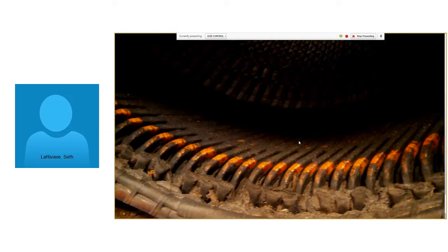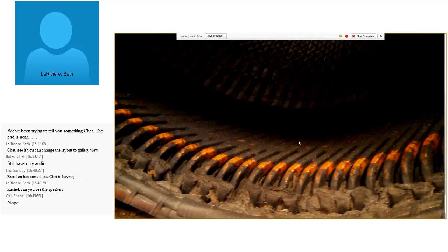Yeah, so this is a video that was done at Oregon State University by a couple of guys that have their PhD in motor science. What they're doing a study on is what happens when there's an actual turn-to-turn short. So they're going to induce a turn-to-turn short in this motor winding. You can see the motor up here. When they hit this knife switch right there where the light is, boom, they just induced a turn-to-turn short while the motor's running.